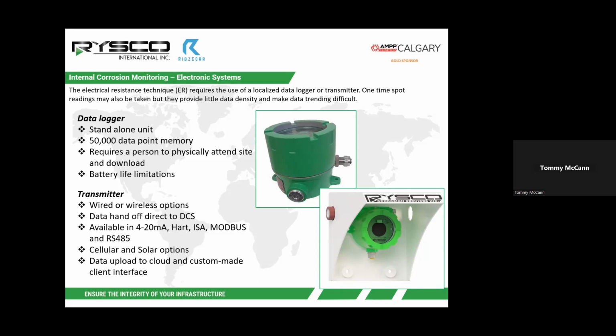The transmitters come in a whole variety of types and designs, mainly based on whether they are wired or wireless, and how they are handing that data off or communicating. Most commonly to your DCS, you'll have 4-20 milliamp, which is one of the first ones ever conceived. More recently, in the last 20-25 years, we've gone towards HART protocols, more recently ISA, and then you have Modbus, and then very commonly RS485.